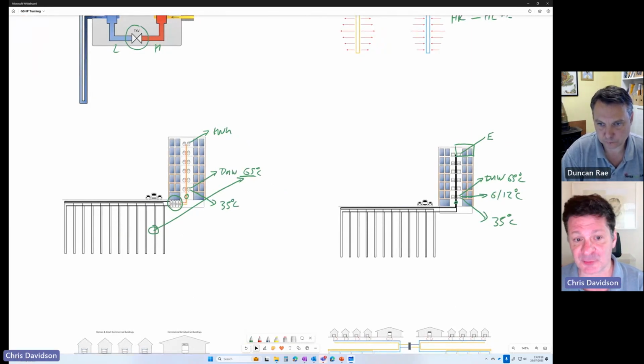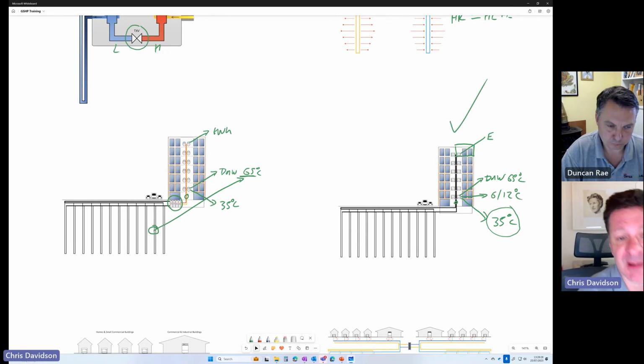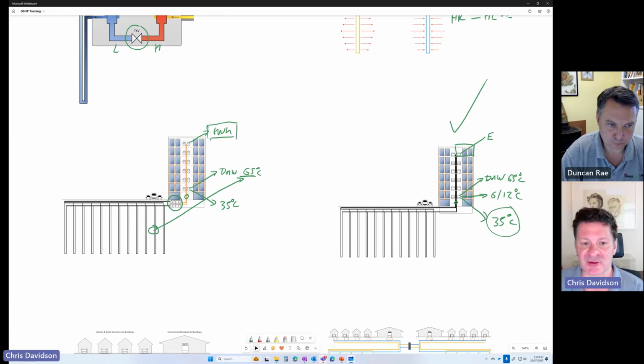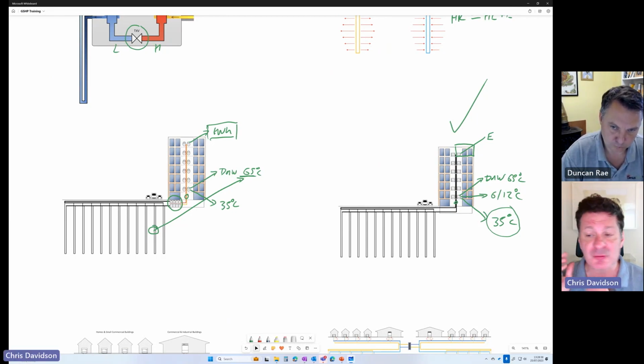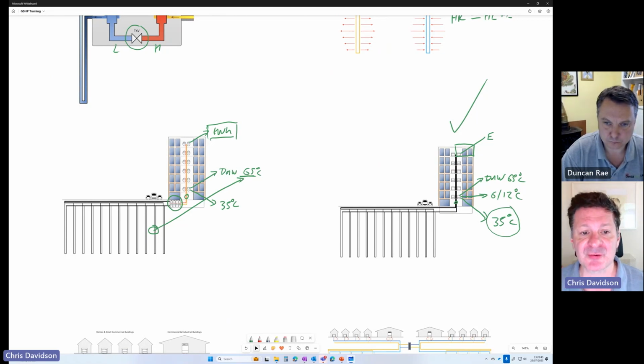Almost always when we do feasibility studies comparing these things back to back, because we are not now compromising that space heating efficiency, this one almost always comes out the more efficient solution. However, the sale of heat agreement here can be very important to the economics of that system. So we've got two different solutions. In terms of installation costs, they are remarkably similar. We did a feasibility study fairly recently where the system installation was going to be £4 million to do the project, and it was £4,000 difference between the two solutions. So they are very, very similar in terms of installation cost.